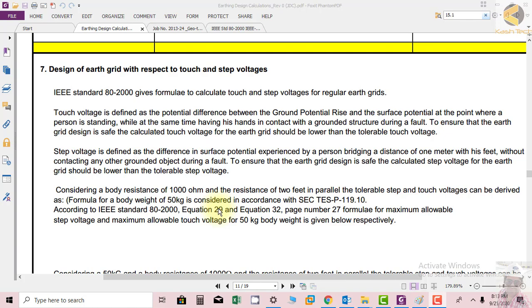Step voltage is defined as the difference in surface potential experienced by a person bridging a distance of one meter with his feet without contacting any other grounded object during a fault. To ensure the earth grid design is safe, the calculated step voltage should be lower than the tolerable step voltage.